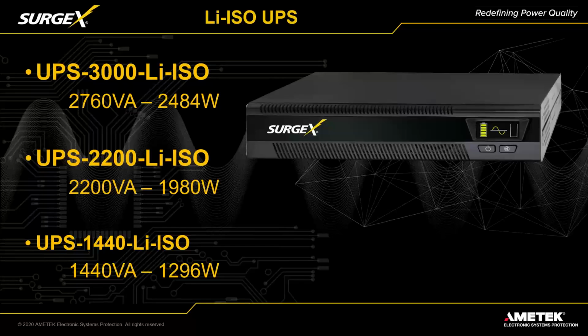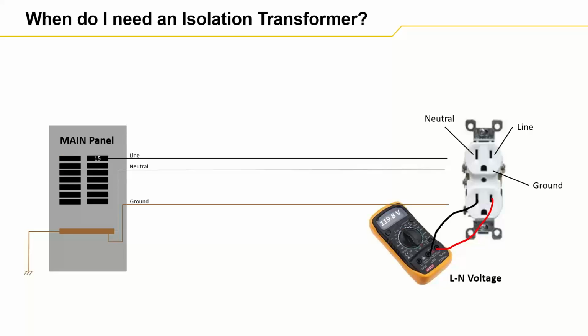So let's talk a little bit about isolation transformers. Why do you need an isolation transformer? It all stems from the fact that neutral and ground are bonded, or connected together, at a single point in an electrical system, and that happens inside the main breaker panel. Therefore, the voltage between neutral and ground theoretically should be 0 volts. Anytime electrically you have something tied together, they're at the same potential, and if you put a voltmeter across it, it should be 0.